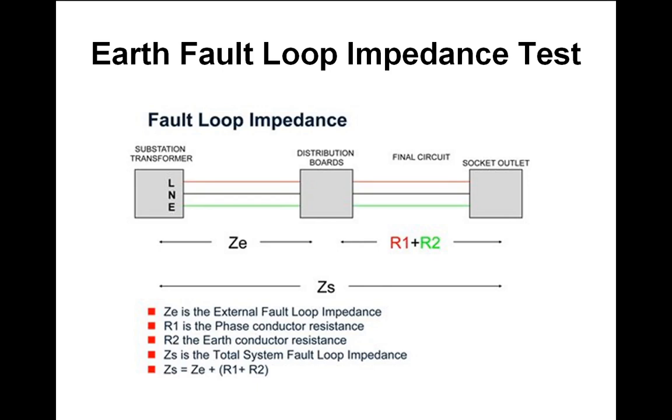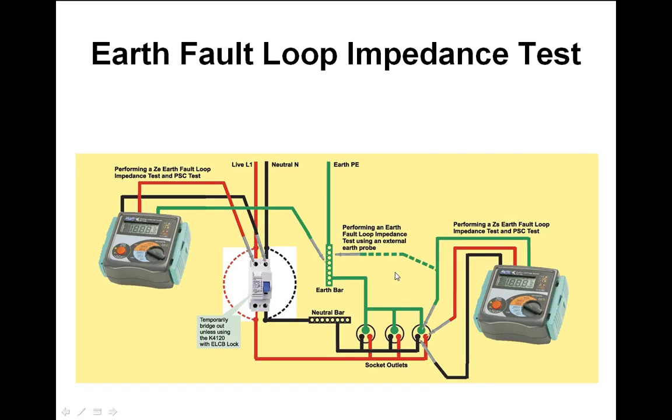that the overload is going to be triggered. For small circuits and the domestic stuff you're likely to deal with, that is not much of a problem. But when you've got a machine that pulls in, say, 100 amps at 240 volts or at 415 volts, a massive motor, then obviously the earth wire needs to be a lot stronger to carry 100 amps and more, sufficiently to let the overload kick in and let the protective circuits do their job if anything goes wrong. Again, this is just another scenario here.